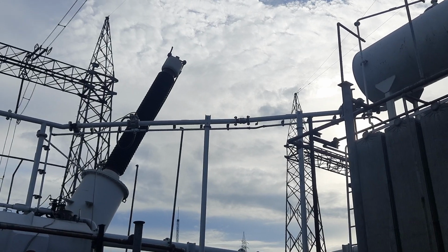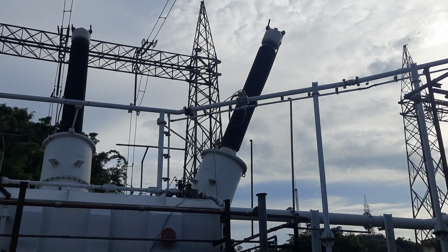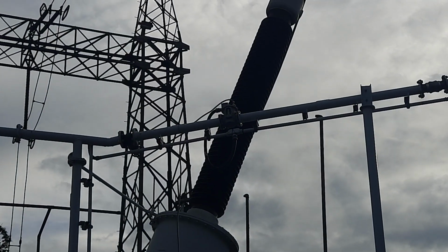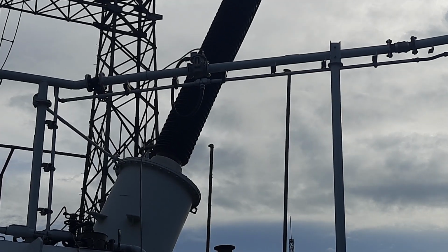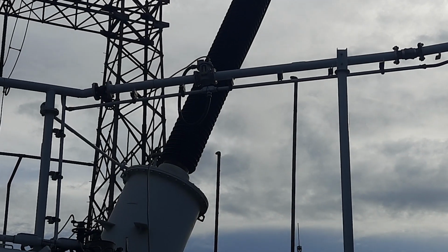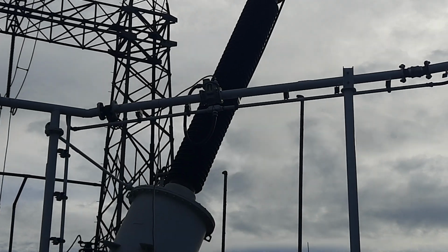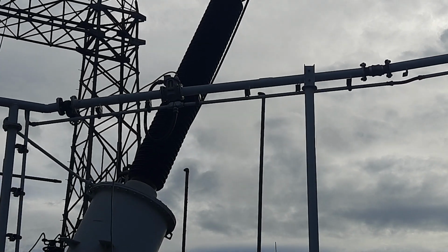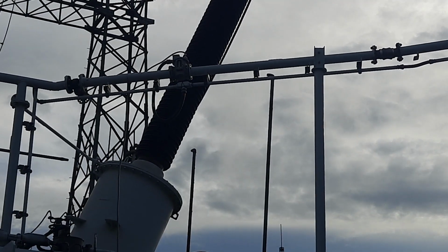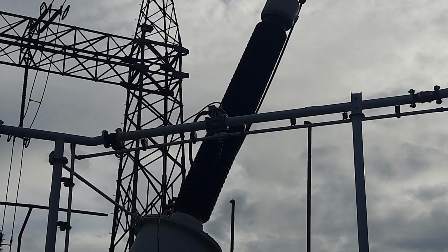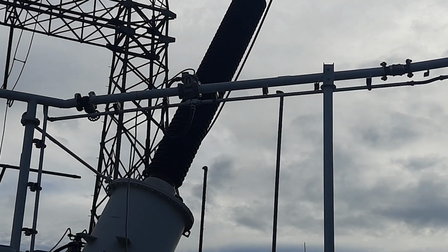While trying to reach the conservator tank, some of the gases will be trapped in this Buchholz relay, and in the upper portion of the relay where oil is there, the gas will take that position and push the oil down. Because of that, the float which has been installed on top, the magnetic contacts will get activated and give an alarm contact, telling someone in the control room that something is happening with your reactor or your transformer, and you have to pay attention to that.